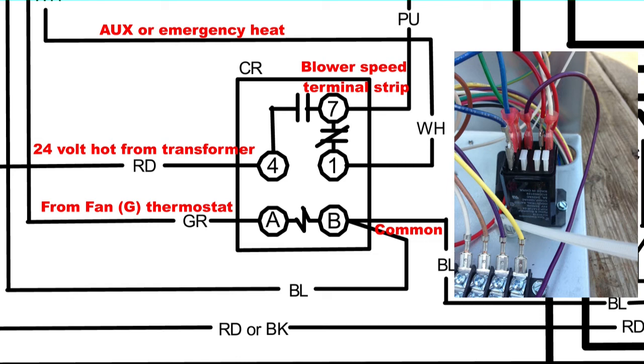As you see, it only uses a single pole. It doesn't use both sides of the relay—it doesn't even include it in the drawing. So what we have is terminals 1, 4, and 7. Between 1 and 7, you see that little equals mark with a slash to it—that means normally closed. If there's no power to the A and B from the GR or green wire, the 1 and 7 are closed.